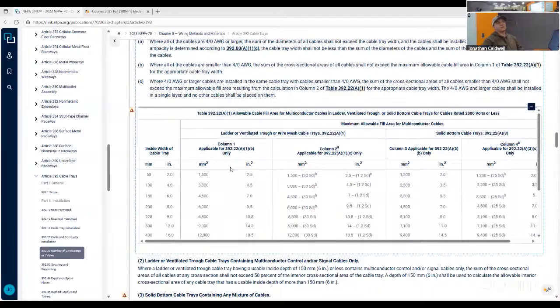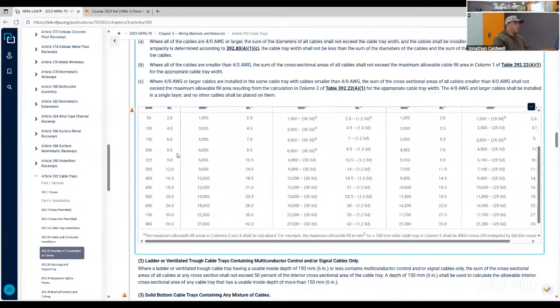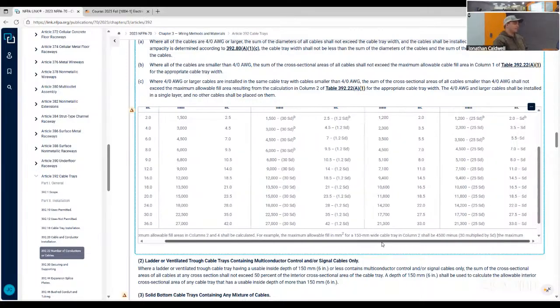So when it says more typical, what we install out there is 6-inch high cable tray. So from top of rung to the bottom of the C channel lip is 6 inches, or should be close to 6 inches. That's the height. The width would be 36 inches or whatever, 24, 18, 12. But you go up the height, and then your width is on the inside, not the outside. Okay. And it's top of rung. It's always above the rung, remember that.